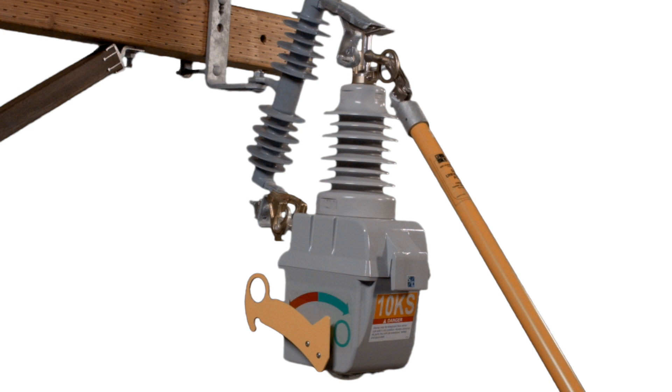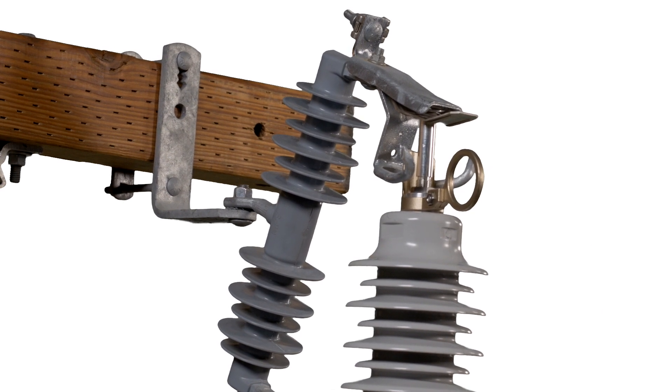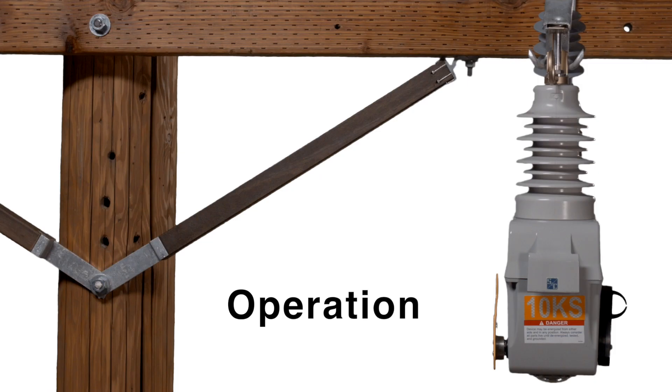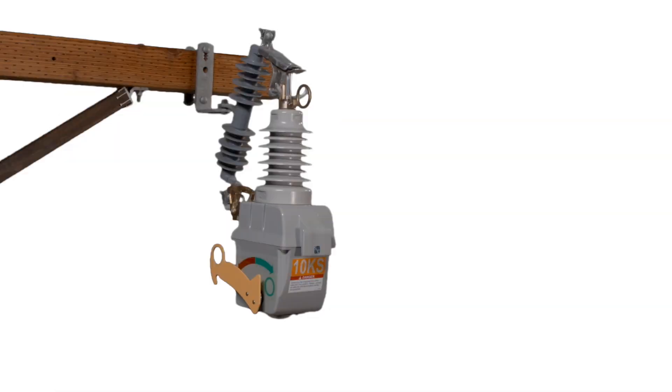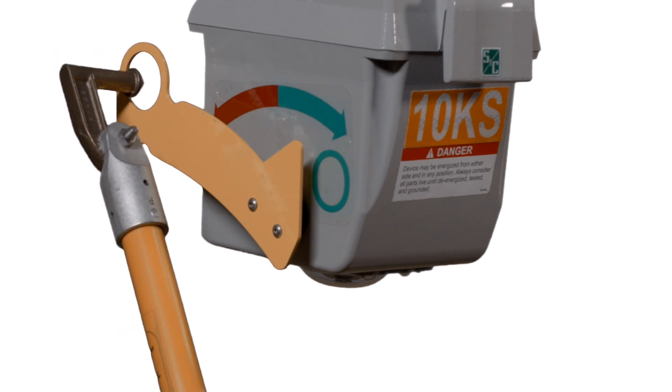Disengage the tool from the pull ring, taking care not to pull the VacuFuse Interrupter open. With the VacuFuse Interrupter closed into the mounting, energize the transformer by pulling down on the open-close lever to close the VacuFuse Interrupter.